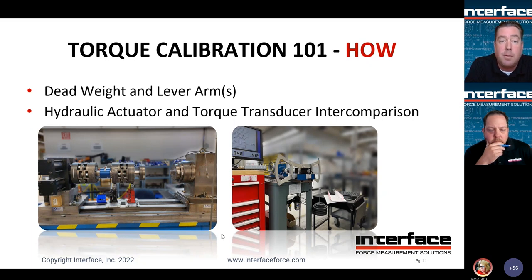And then the other method, past a certain point, we transition to hydraulic actuation. So the image on the left is our hydraulic stand. This is about a 100,000 pound-inch stand. So we have a hydraulic actuator and a torque transducer in line. And there's a gap there you can see where we would fit our DUT in line. Next slide, please.